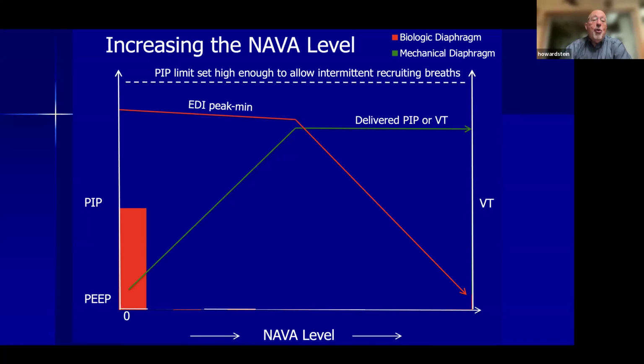This is a graph where we're looking at peak pressure on this side, tidal volume on this side. The green line is the amount of peak pressure or tidal volume being delivered. And the red line here is your EDI, your phasic EDI, which is the peak minus the minimum, which is what the formula looks for. And the red bar over here is the biologic diaphragm, and the green bar is going to be the mechanical diaphragm. So this is what we would like to deliver up here. And this baby's in respiratory failure, so you can see he's unable to get the size breaths that he needs.